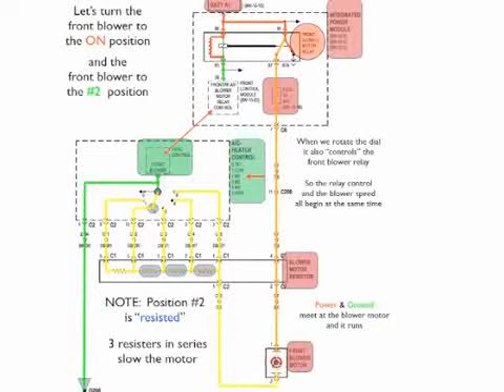But notice that we've got connections at 1, 3, 4, and 5 as well. Now you may be asking, why is that? Well, before on position 5, it was connected directly to ground, and now it's number 2 that is connected directly to ground. But 1, 2, 3, 4, and 5 are all directly connected to each other as far as continuity goes. The wires are physically touching, and there's no opens in them. So when we switch to any position, for example here in position number 2, we're going to change that from a ground to a switched ground, and it's going to turn yellow, and all of those wires that are connected are going to turn yellow or have ground at them. So if you were testing this switch, you would have ground at all of those pins.